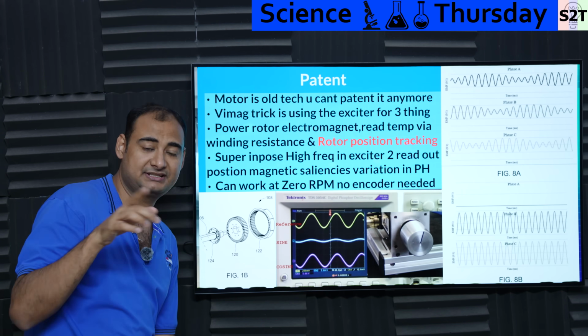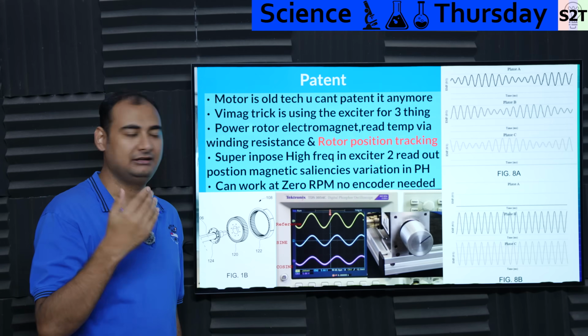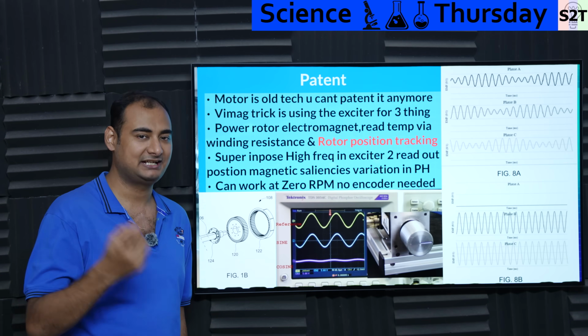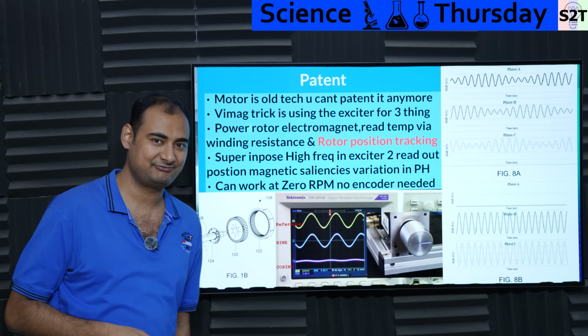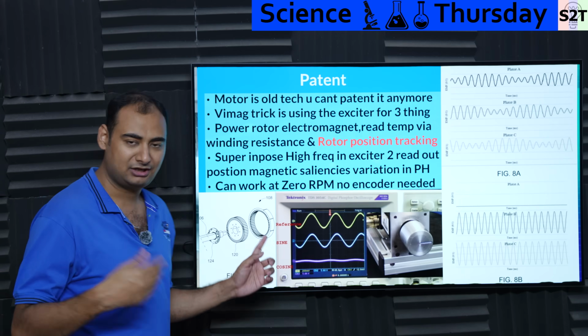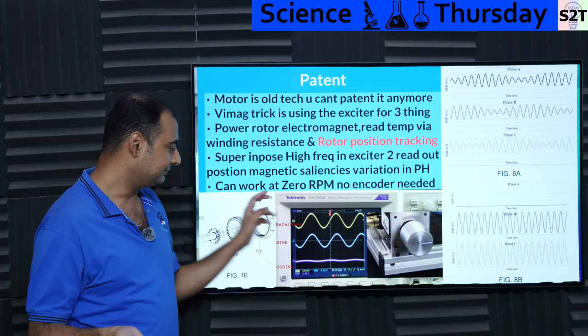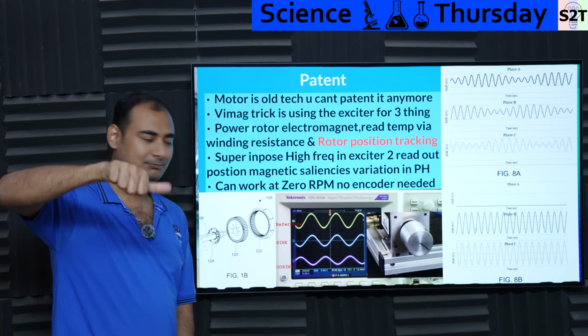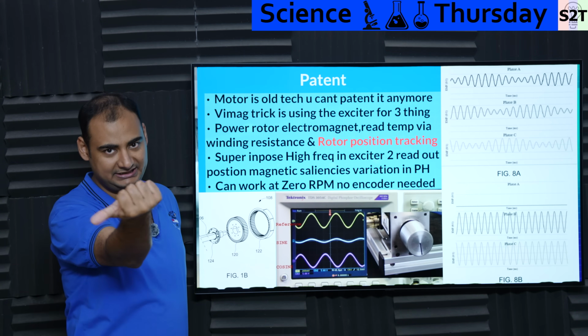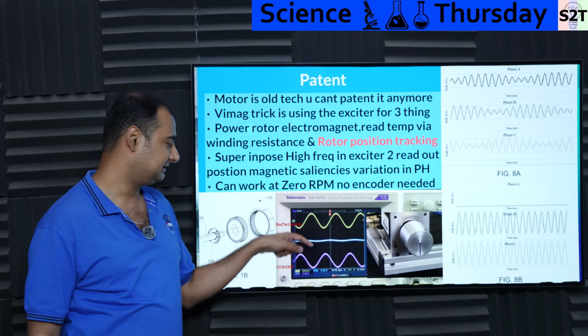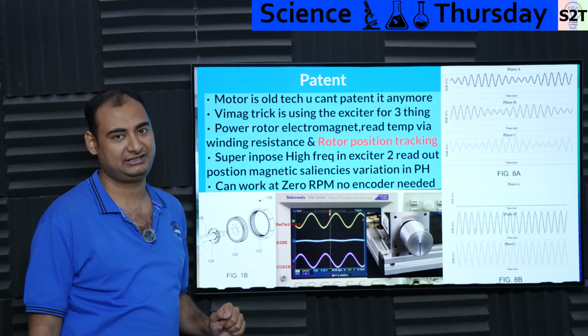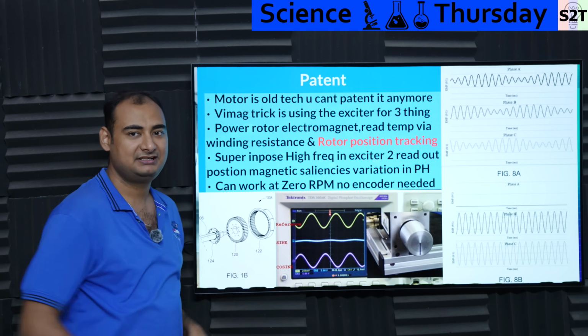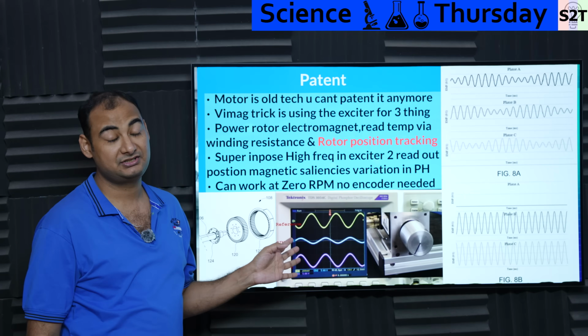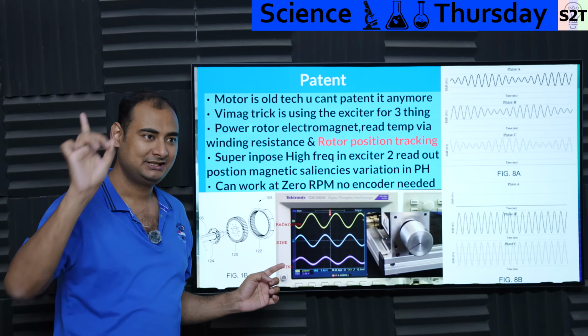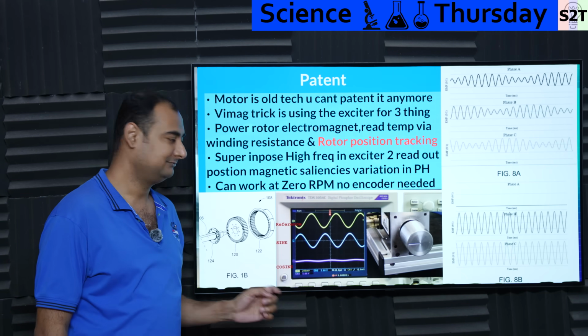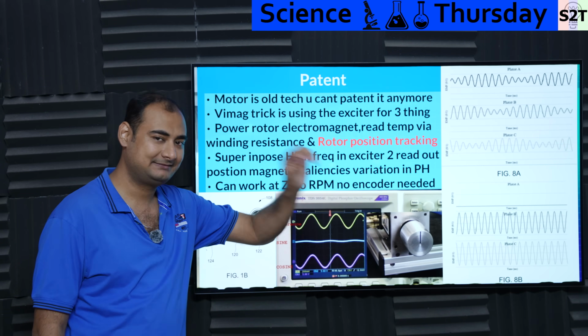Because it's high frequency, it will work even at zero motion. If you send DC, it requires spinning, that's why we used to use it for generators first. Now you can make high frequency without any issue. So that reference signal goes based on the position of the rotor, and you can easily figure out whether sine has a high value or cosine has a high value. Subtract these two, they destructively interfere, giving you a new waveform. That waveform is your rotation, basically where you are, exactly, precisely.